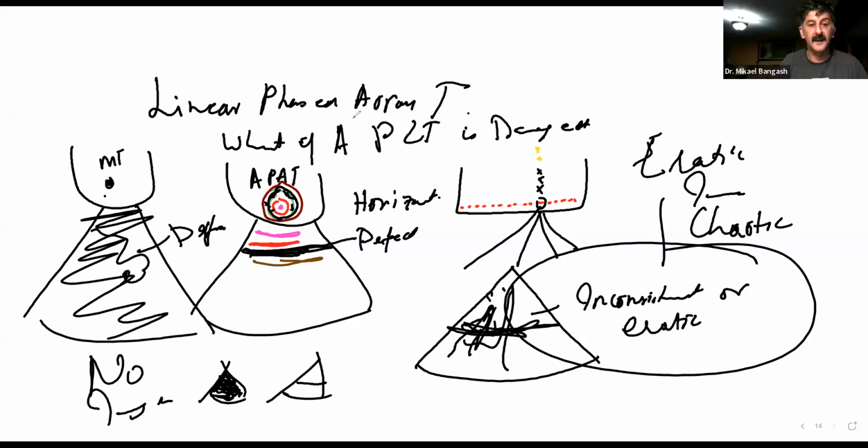For your linear phased array transducer, we really can't tell by looking at it. Crazy things may happen on the image. We can't say it is this PZT that is damaged, or that one. If either one or two was damaged, it could lead to the same defect on the image.